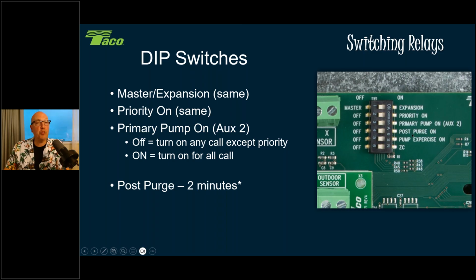Now we also have post purge in here, which we've had before, which means last zone calling. We're going to keep that zone on for 2 more minutes if no other call happens. So I have, say, a cast iron boiler or a high mass boiler. Let's take those BTUs out of the boiler and dump it into the last heating zone, rather than just sitting in the boiler to go up the chimney and see you later forever. All right, so let's take those BTUs out and drop it into the house itself. All right, so there's an asterisk there, which means it's programmable as well. I can change that time, and I'll show you guys how to do that too.